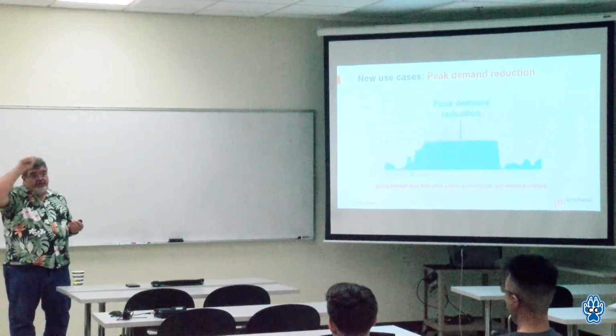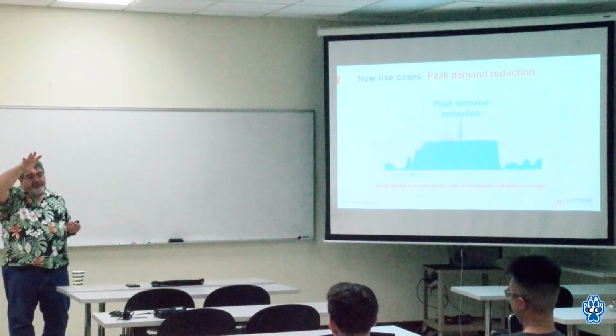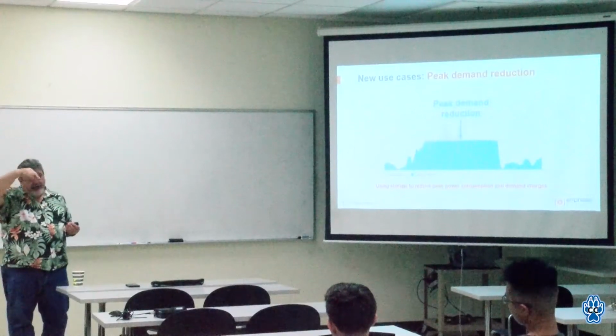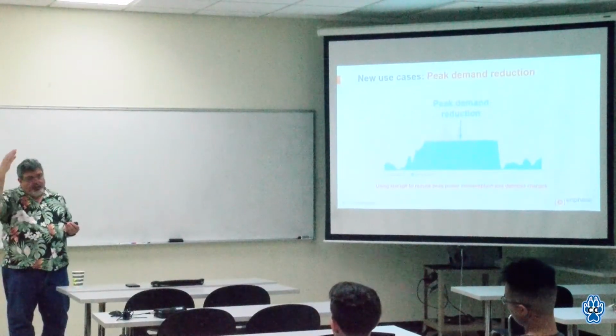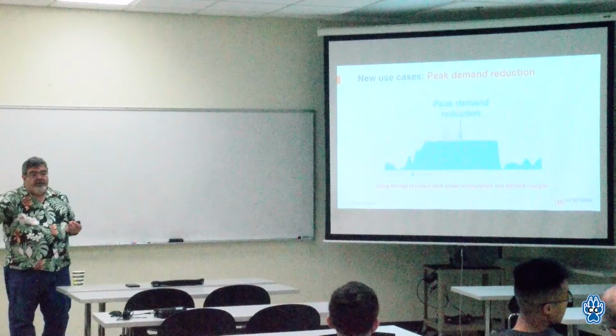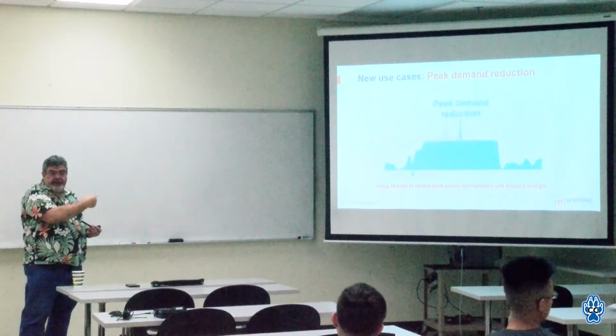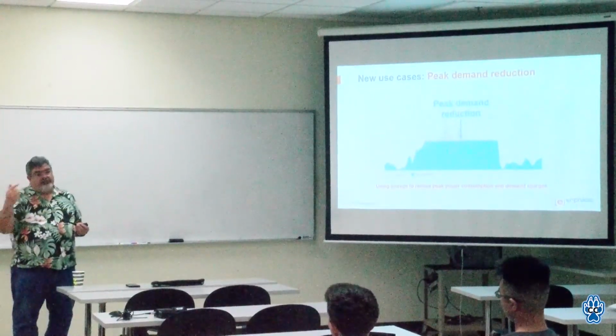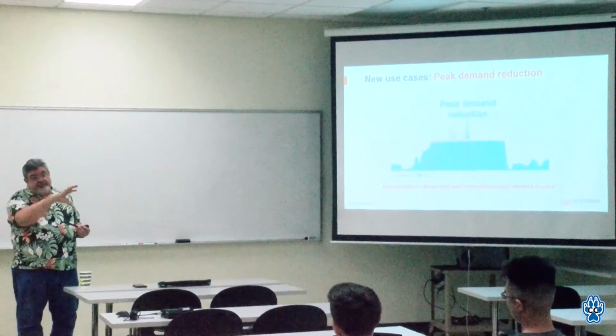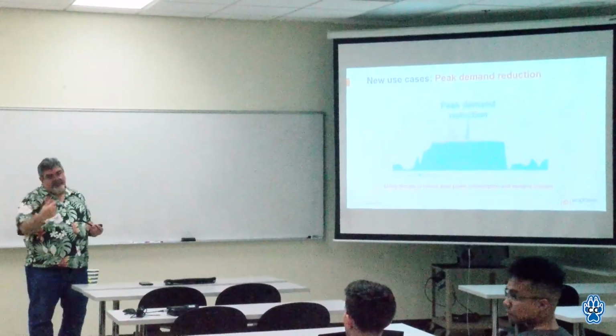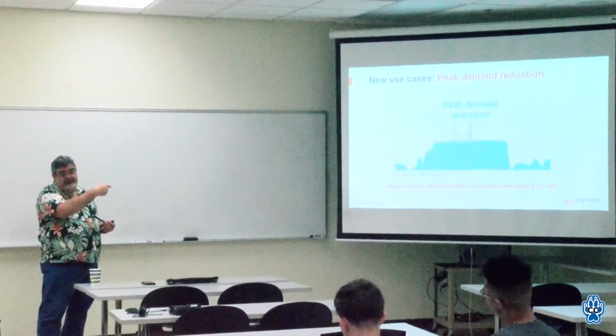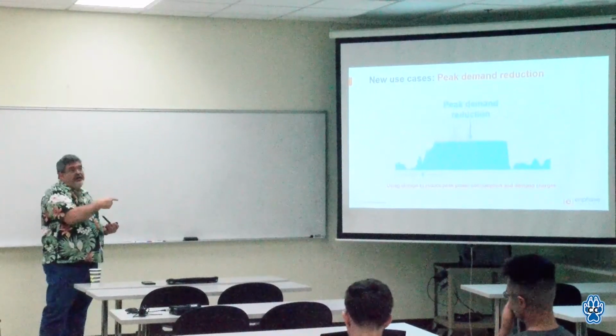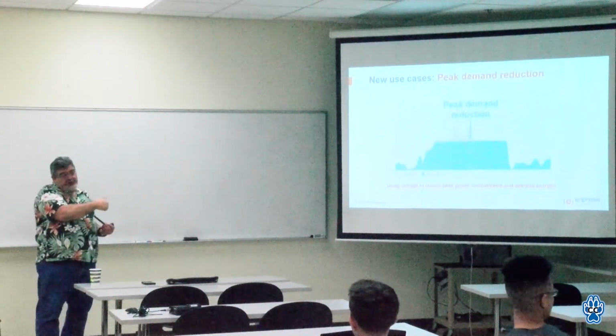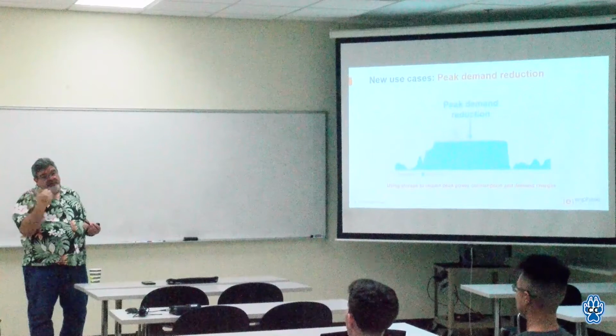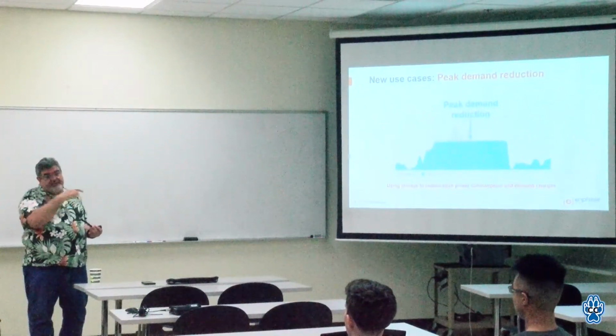But if you look at the power path from the module, yes, it's DC out of the module. It goes through power conversion to AC, onto your panel board, your circuit breakers, and then you have another branch circuit with your batteries on it, which takes that AC and converts it to DC through a regular power supply, charges the battery, and then has to return that energy back to the grid, converting it back from DC to AC.